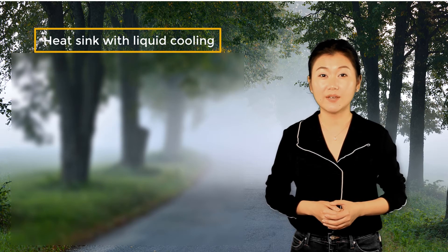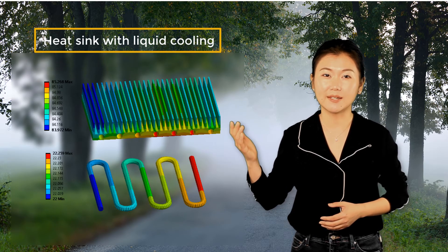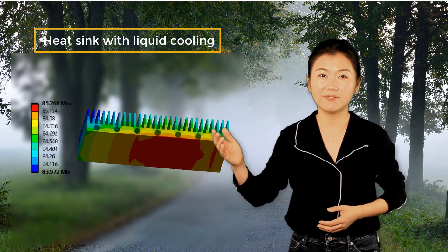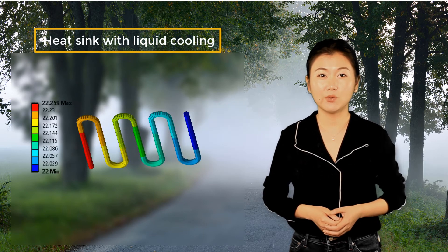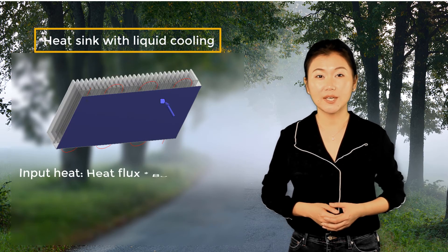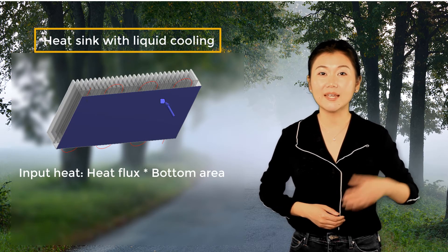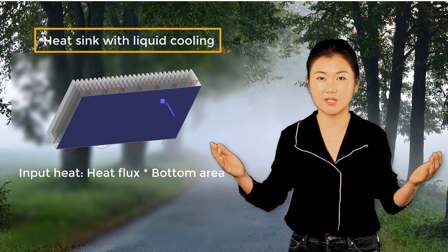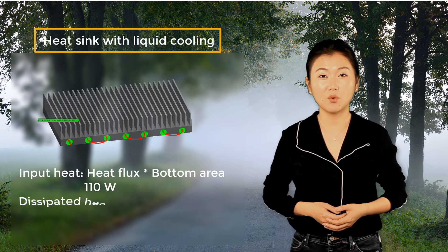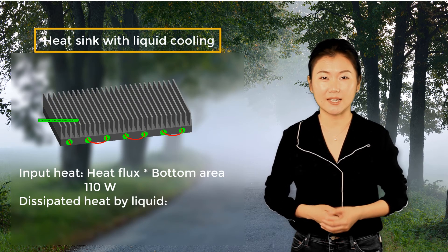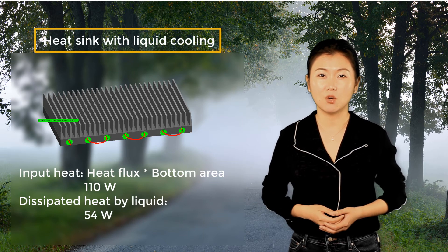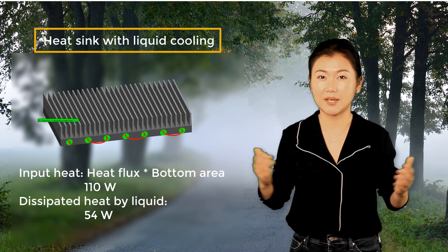Running the simulation will give us the following temperature distribution on the heat sink and the fluid. The overall temperature on the heat sink is around 85 degrees Celsius. The temperature of the liquid is gradually increased as it flows through the passageway. We can find the input heat of the system by multiplying the heat flux input and the area of the bottom surface, which turns out to be 110 watts. If we do a probe on the convection boundary condition between the fluid and the heat sink, we can see that the energy rate the liquid takes away is 54 watts. So a great amount of the energy is dissipated by the liquid cooling.